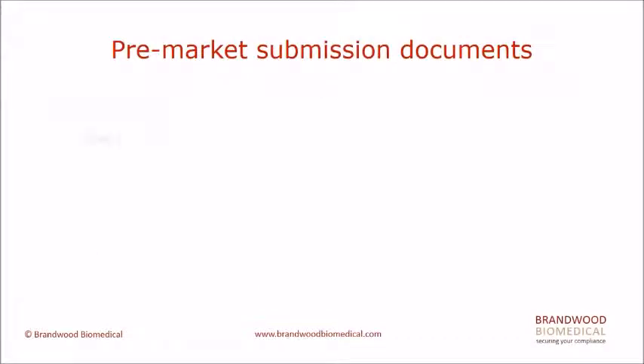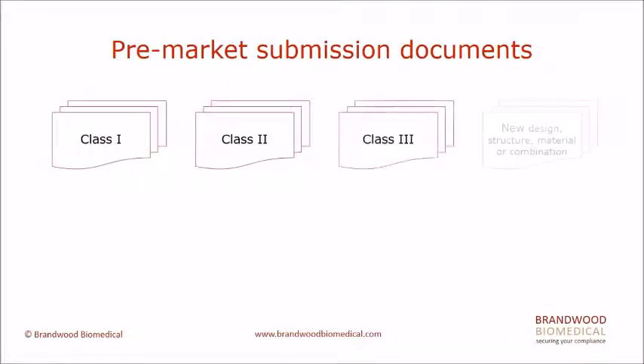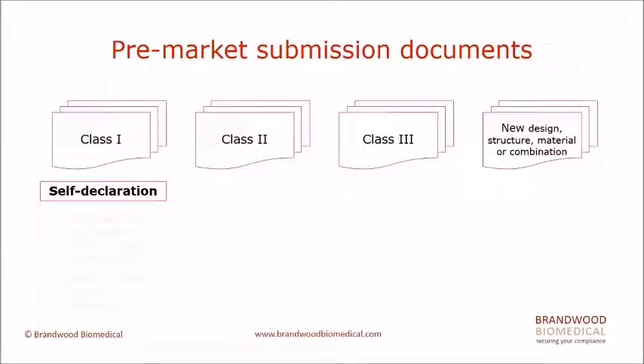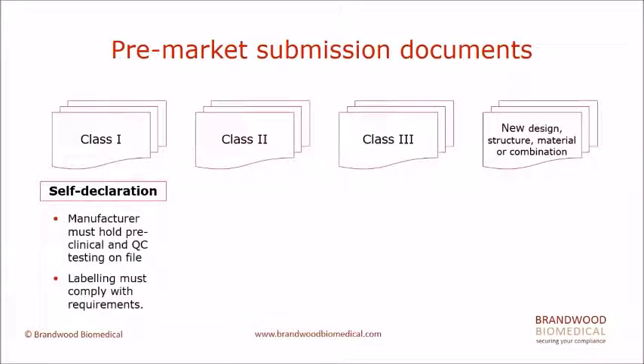This is an overview of the pre-market submission documents across Class 1 to 3 and the novel devices. For Class 1 devices, it's purely the administrative documents, which are all self-declarations. Even though the preclinical testing report and the QC testing reports are not part of the initial submission, the manufacturer must hold those testing reports on file, as they are subject to post-market activities. And the labeling also must comply with the Taiwan requirements.